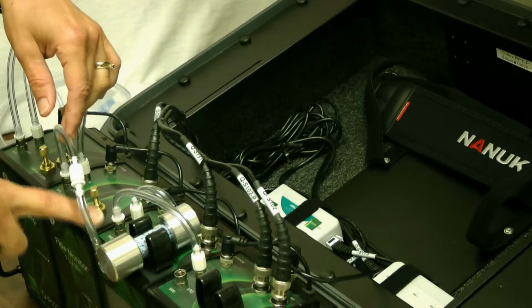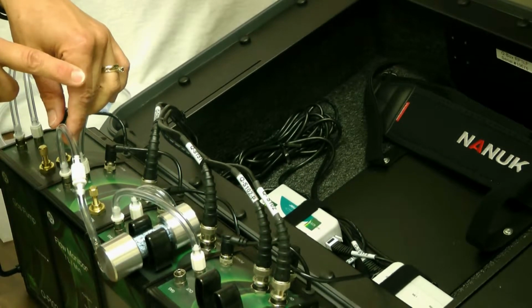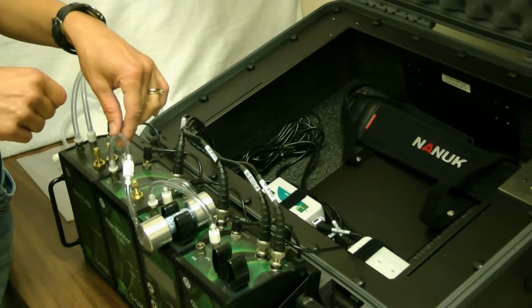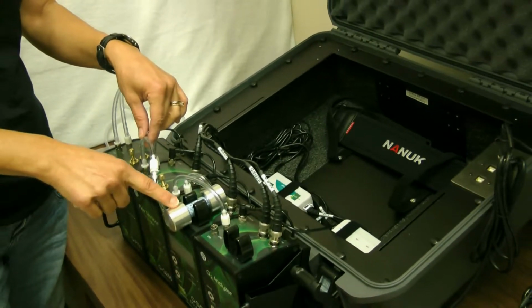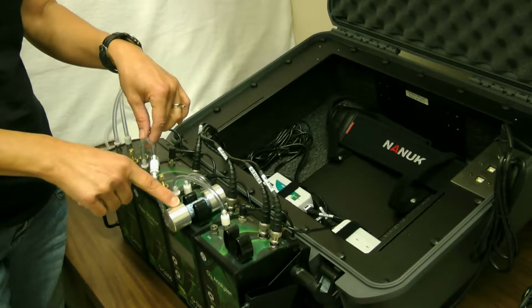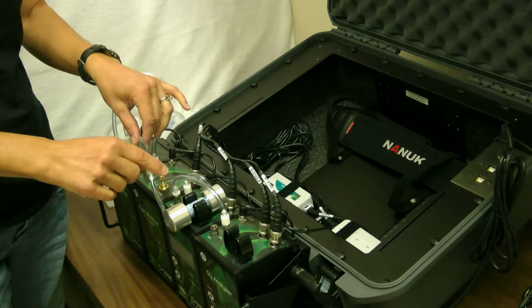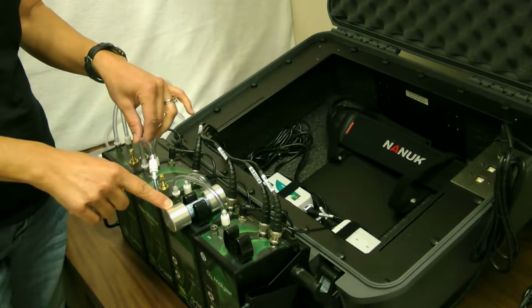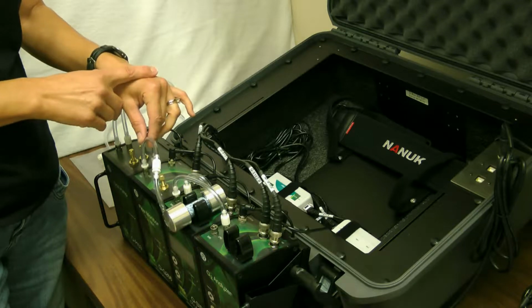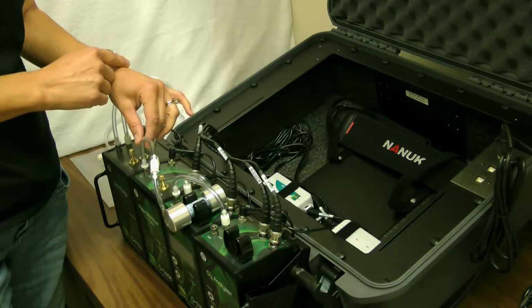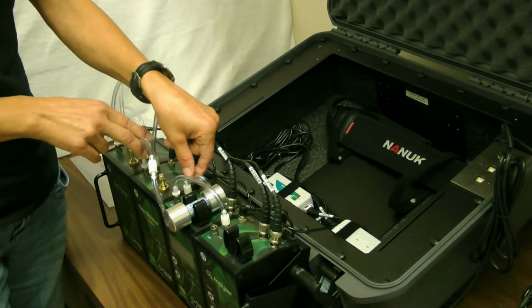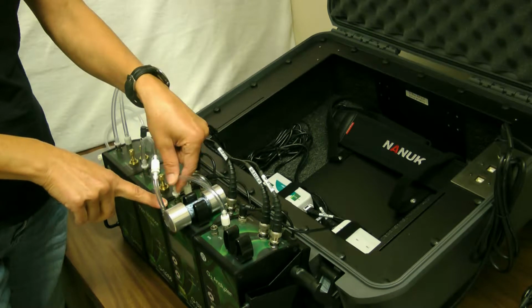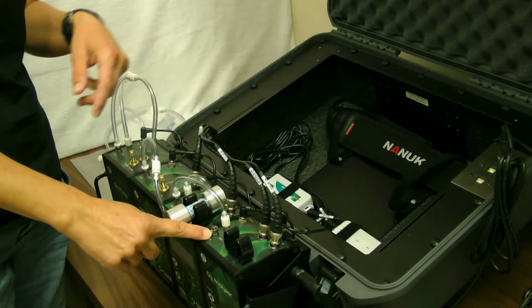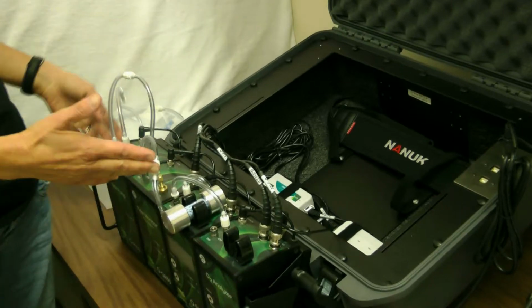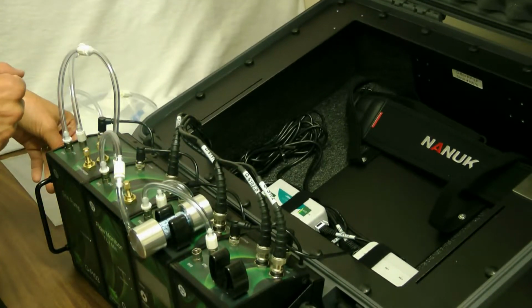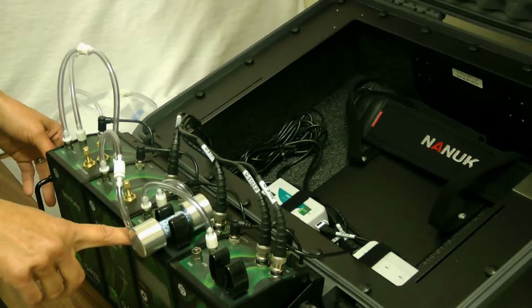The gases measured by the CO2 and oxygen analyzer should be dry to prevent any dilution of the gases with water vapor. And we provide a drying column with Drierite, which has a blue indicator that will turn pink when the Drierite is spent. That gives you an indication when you need to change it. And we do supply in the kit some extra Drierite, but this can also be regenerated in the oven. From the Drierite column, the gas enters the CO2 analyzer, and then after the CO2 analyzer, it is carried to the oxygen analyzer, and then it vents out from the oxygen analyzer when the system is used in open flow mode. So the way that this is plumbed right now, it's set up for calibration.